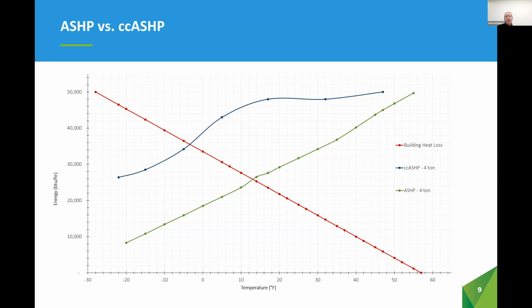Both 4-ton units fall within the 70 to 105% sizing recommendation by NRCan. Specifically, the standard air source heat pump's rated heating capacity meets 88% of the building's heat loss, and the cold climate unit meets 96%. So let's do a quick thermal balance point analysis to further compare these units. The thermal balance point refers to the outdoor air temperature where the heat pump's heating capacity is equal to the heat loss of the building.